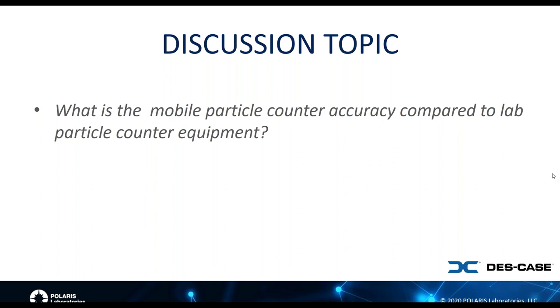Well, that's a pretty good question. Of course, I'll be a little biased in what I'm going to say, but the test in the lab will be much more precise than a mobile particle counter. The mobile particle counter will just give you an idea of the particles that you have present, but I don't think that it will actually break it down into particle size ranges.